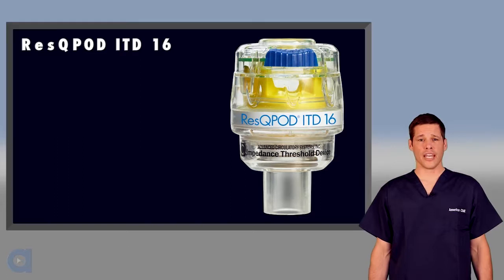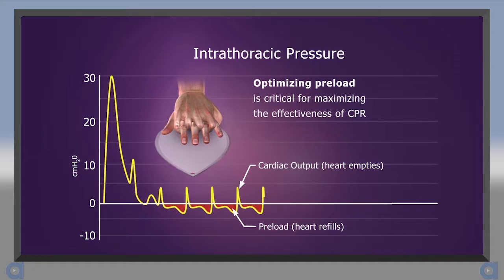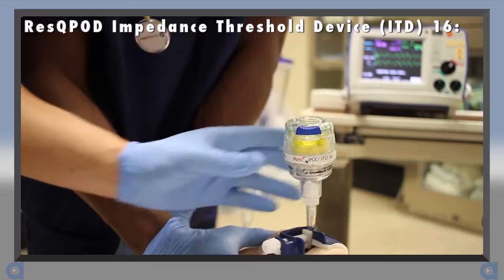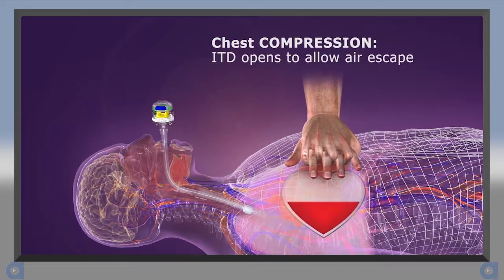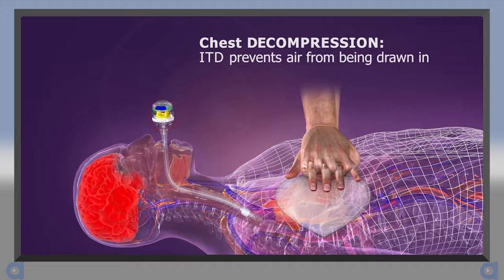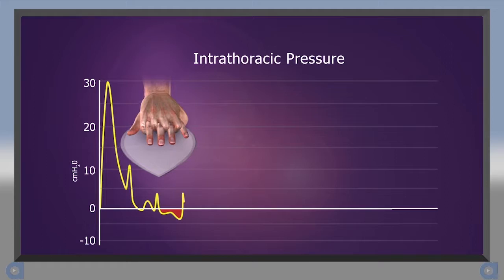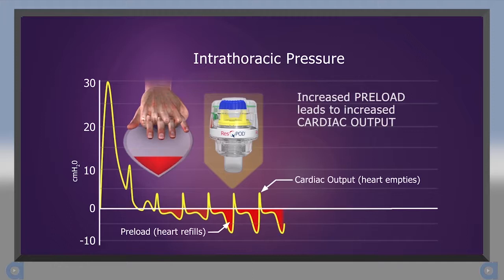Let's begin by talking about how the ResQPOD ITD-16 works. Recall that during CPR, positive pressure helps to circulate blood forward, while negative pressure, or a vacuum, helps to refill the heart. An impedance threshold device, or ITD, fits into the airway circuit on a face mask or advanced airway. During chest compression, the ITD's valve opens and air is forced out of the lungs and through the ITD without resistance. But as the chest wall recoils, the ITD's valve closes and prevents air from being drawn back in. Preventing the influx of air enhances the negative pressure, which pulls more blood back to the chest and heart. The increased preload results in increased cardiac output on the next compression.